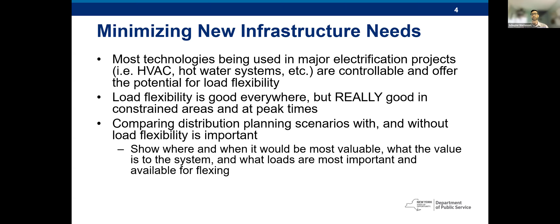The first is a timing issue. On the distribution network, utilities typically like to have at least a year to study everything, and if they find something they need to build, they need 3 to 5 years to build it. That's not at all how load is actually developing nowadays. These big loads can come in overnight. I can go out and buy an EV today, and my neighbors could do the same thing, and you go from a neighborhood block with an average house load of 3 kilowatts to an average house load of 10 kilowatts the next day. That's a huge change that's not in typical forecasts, especially on these very localized systems. System upgrades can take a long time, but system growth does not take very much time at all. So there's this timing disconnect we have to solve for and make sure our programs and plans account for.